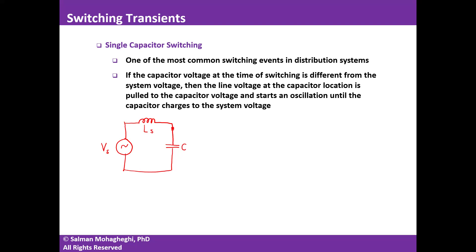As we have seen before, the moment I close a switch to connect the capacitor to the rest of the system, I will have an oscillation. The voltage of the capacitor follows the form: V minus the difference between the system voltage at the moment of switching and the initial voltage of the capacitor, times cosine of ω₀t, where ω₀ = 1 / √(L_S · C). These events are high frequency enough that we can assume the system voltage remains constant during the transient.